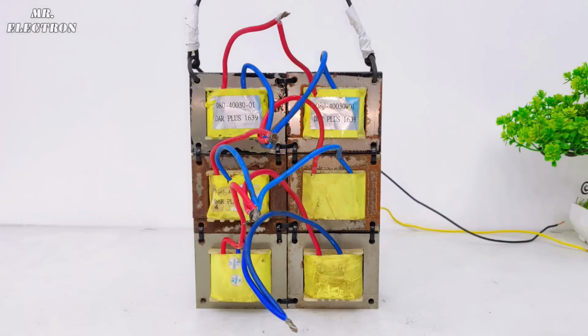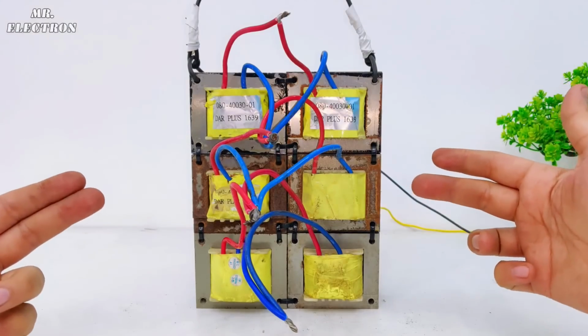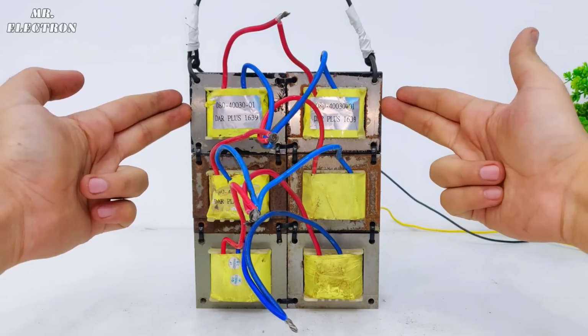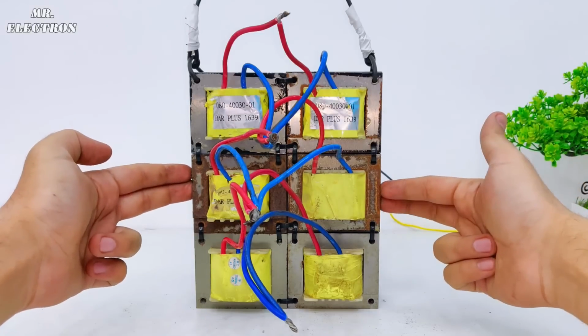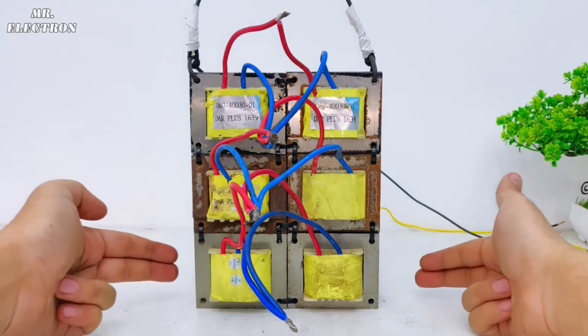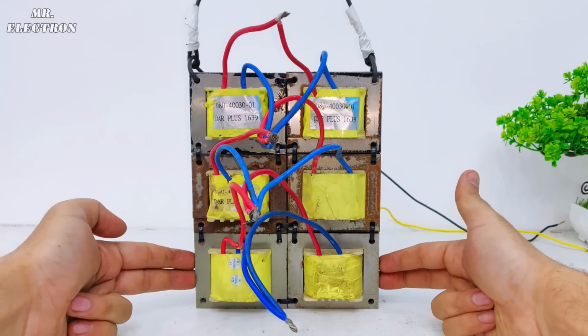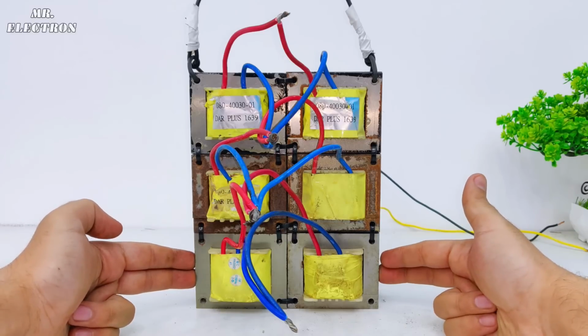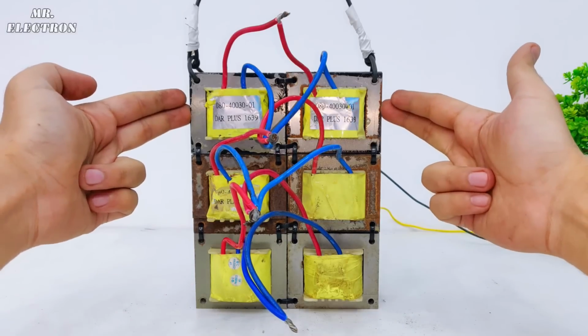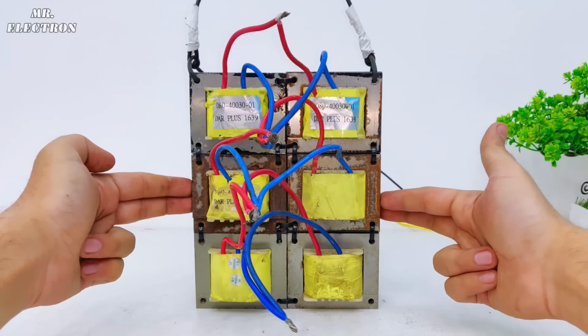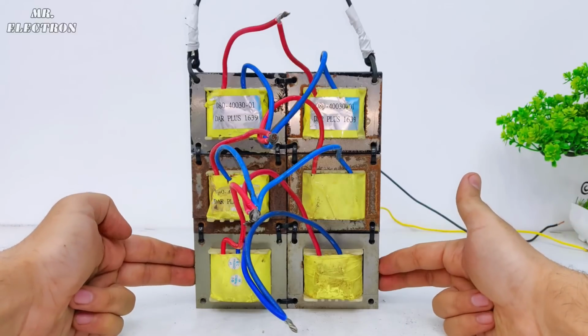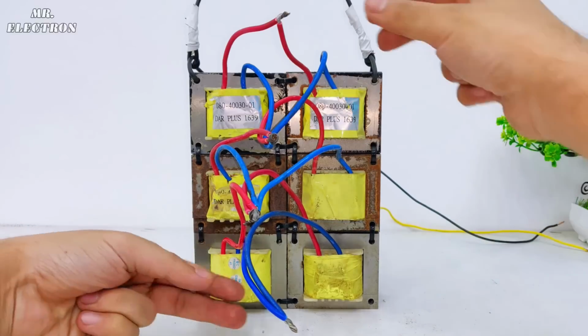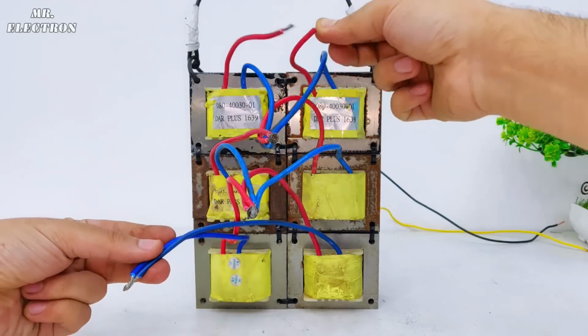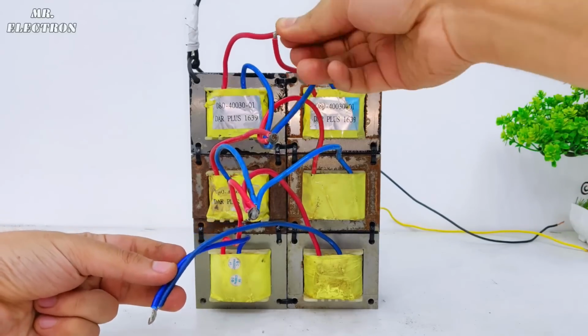By connecting the wires like this, I've connected the first 2 transformers together in parallel, the same for the next 2 transformers, and parallel for the last 2 transformers. At the same time I've connected the first set in series with the second, and the second in series with the third, and the overall output will appear on the first and last set wires.